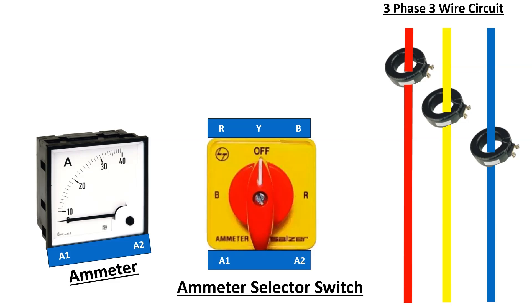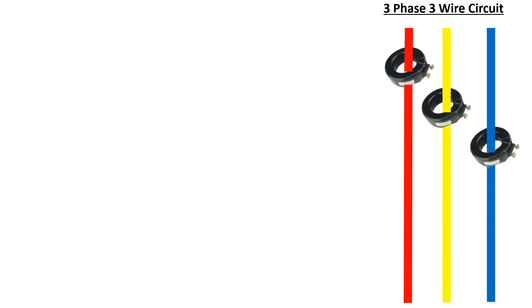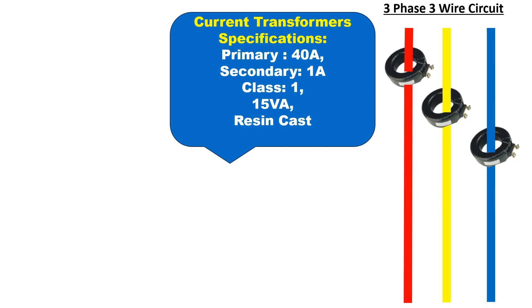The ammeter selector switch allows you to monitor the current in each of the three phases separately. I want to know how to connect the ammeter and ammeter selector switch in a three-phase three-wire busbar to measure the current. In an electrical switchgear, a three-phase three-wire busbar arrangement will be like this.